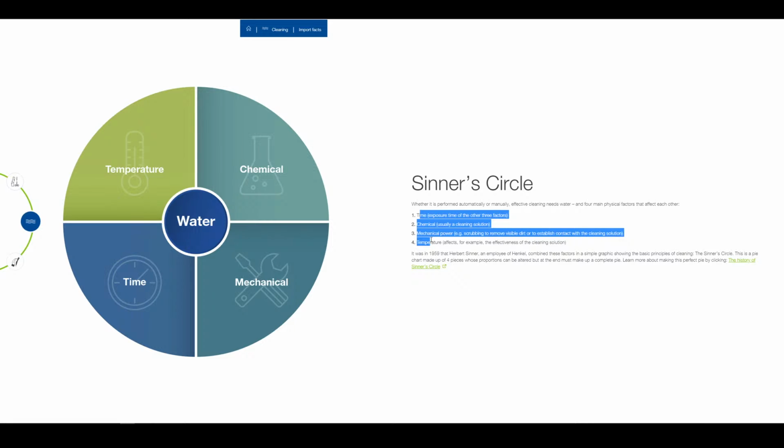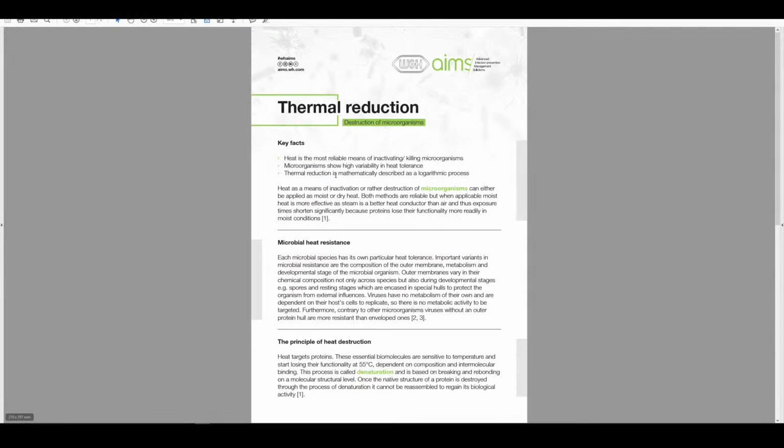Manual cleaning, then I further scroll and I enter automated cleaning. We have thermal washers. Again, we have here a PDF. This shows what is the performance of a thermal washer in terms of cleaning and disinfection. We have also some links here. We talk also about lubrication of our handpieces. We have also some links to the corresponding products we may offer in the specific steps.